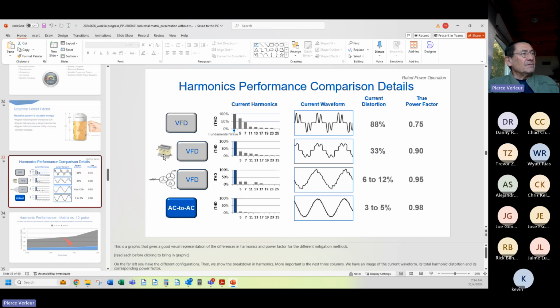This is a VFD with a little filter in front of it. This happens to be a VFD with a 12 pulse or 18 pulse. In this case, at 6%, it would be 18 pulse. At 12%, it would be 12 pulse. And here you're starting to get into the range where the waveform looks kind of sinusoidal. It's not so distorted. And you get your power factor up to where you need it to be, but only at full speed, full load. This passive filter technology, as I said earlier, doesn't work as you vary the speed.